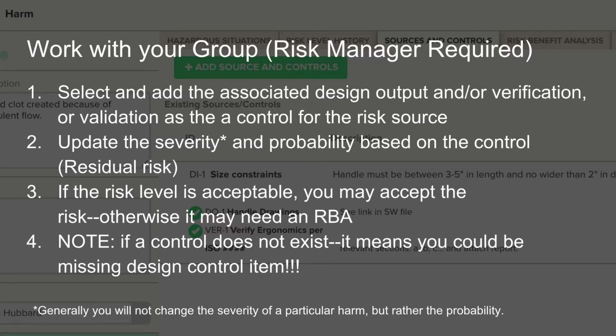And as a reminder, if a design control doesn't exist, it probably means you need to add a design control item. Just like if the source of your harm doesn't exist in your design control matrix, you may need to add a design input or user need.